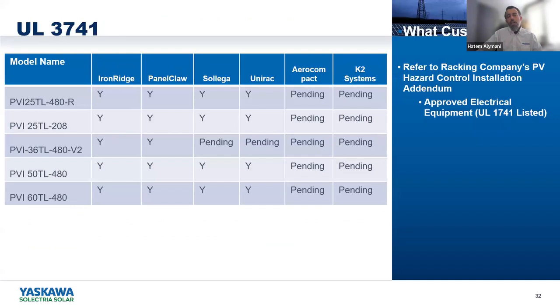UL 3741 is a standard that aims to provide some room and some space that will allow you not to use the rapid shutdown devices. Now, this standard is relatively new, and it's not really adopted by most AHJs. So before you go ahead and design your system utilizing this standard, please talk to the AHJ and make sure that they are accepting this. Of course, during the permitting, they should review this and they should flag it if they're not going to pass it. But the standard is very strict and has a lot of requirements. For example, the inverter itself needs to be located on the roof about 2 feet away from the array. All the strings in the array need to be continuous.